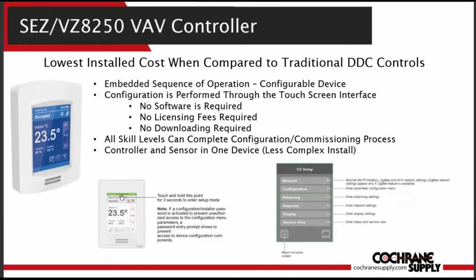The 8250 series controllers can save you money when compared to traditional DDC. As I mentioned, there's no software or licensing required. One device is mounted on the wall as compared to installing a controller in the control enclosure and mounting a separate temperature sensing device on the wall, or multiple if you need humidity, CO2, or occupancy sensing. The configuration is done through the touchscreen interface, so engineering doesn't have to create a program that has to be downloaded to the controller. No computer is required. Configuration is simple and straightforward, so technicians or electricians of all skill levels can configure and install the room controller. In the end, saving time and skill adds up to a lower total installed cost.